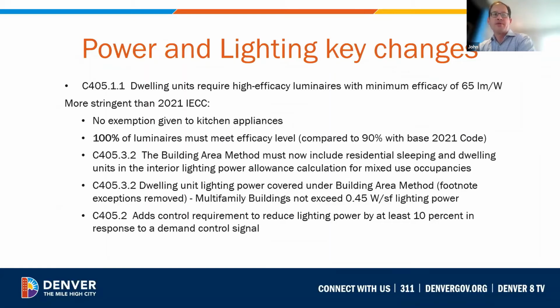First, let's go through just a brief summary of the key changes to the power and lighting sections of the Denver Energy Code. There are new prescriptive changes to commercial lighting requirements. The Denver Energy Code requires all luminaires in dwelling units to be high efficacy lamps with a minimum efficacy of 65 lumens per watt. Now, this is slightly more stringent than the 2021 IECC, which allows up to 10% to be lower efficacy.